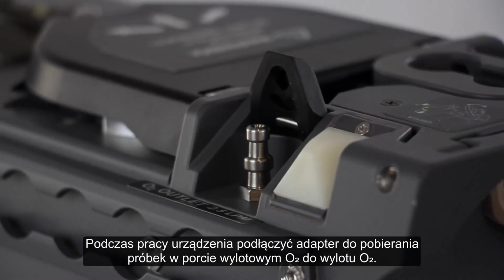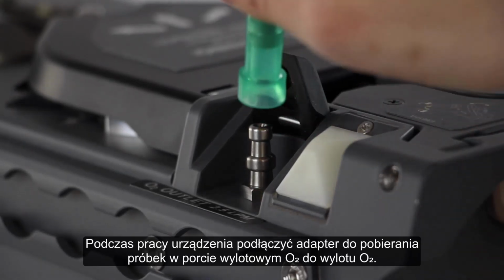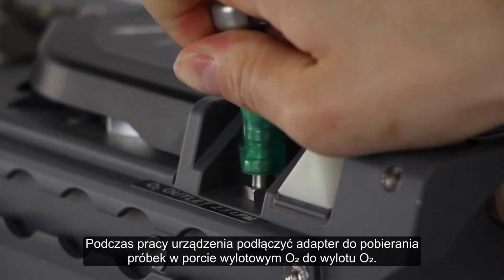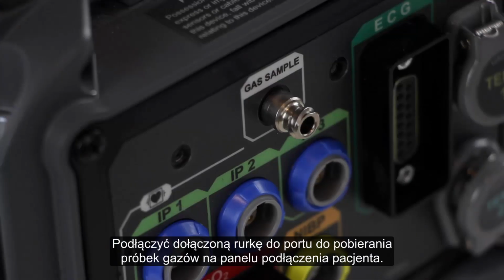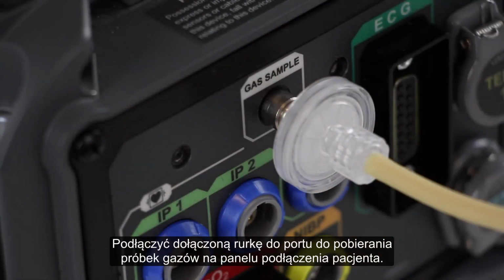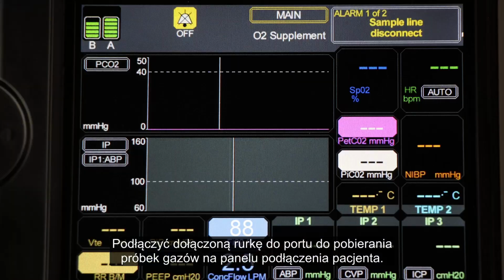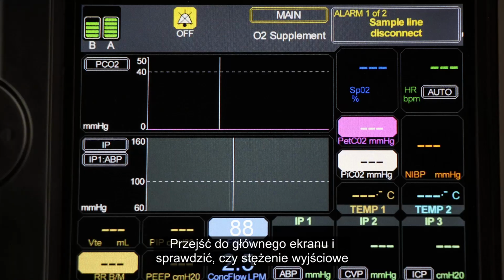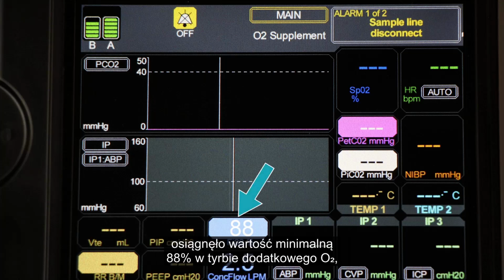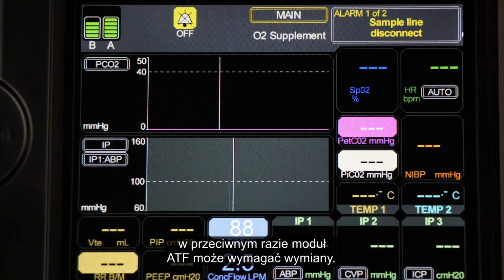While the device is still running, connect the O2 outlet sampling adapter to the O2 outlet. Connect the attached tube to the gas sample port on the patient connections panel. Navigate to the main screen and ensure that the output concentration reaches a minimum of 88% in O2 supplement mode. Otherwise, the ATF module may require replacing.